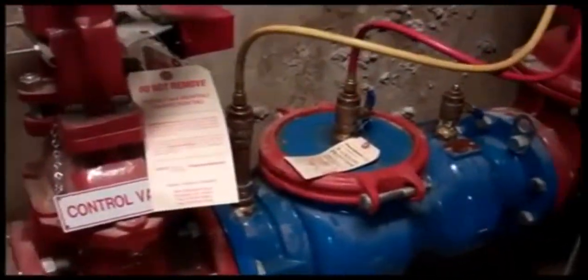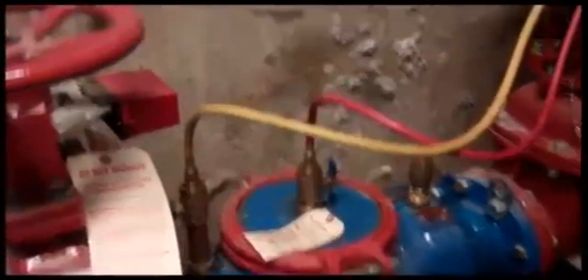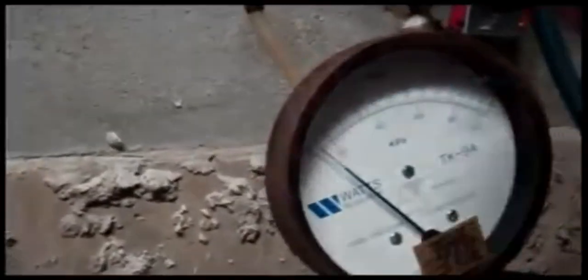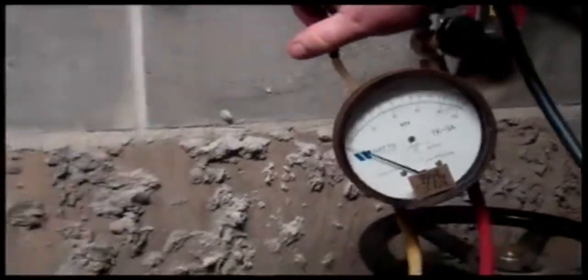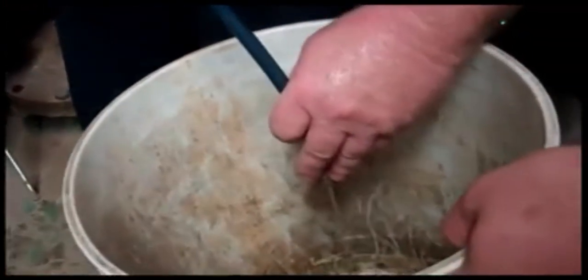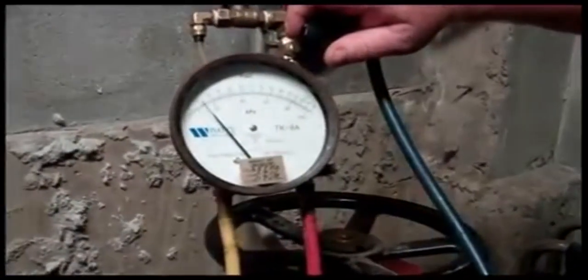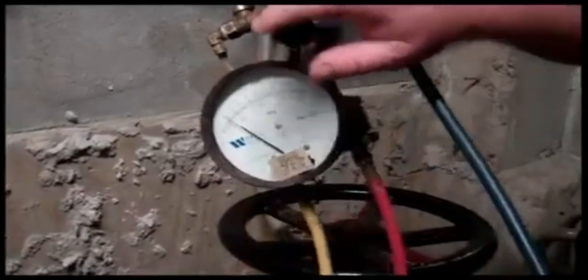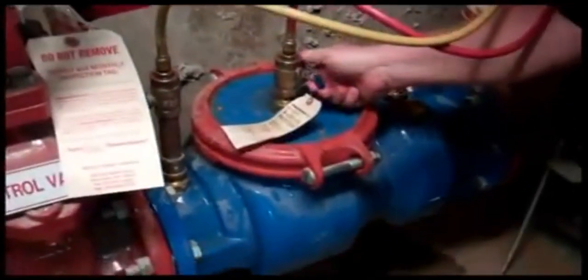The technician opens the test cocks on the backflow device, verifies that all those connections are tight, and then bleeds any air out of the backflow test kit. The valves are then closed, and the pressure difference between the front side and the back side of the first check is recorded.